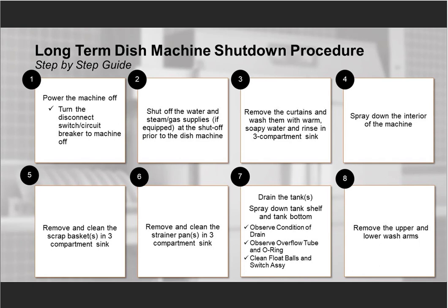Observe the condition of the drain. Does it move freely? Observe the overflow tube. Make sure it has an O-ring on it. Clean the float balls and switch assembly. You want to look at that overflow tube and make sure it doesn't have any splits or nicks in the O-ring. There can be food buildup or metal shavings on the float balls.